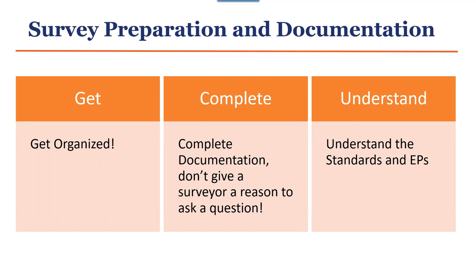If you have a device that fails during testing, maybe it's a smoke detector or a pull station, we expect to see failures. Our spidey sense goes up when everything's perfect, because nobody's perfect 100% of the time. We expect to see failures.